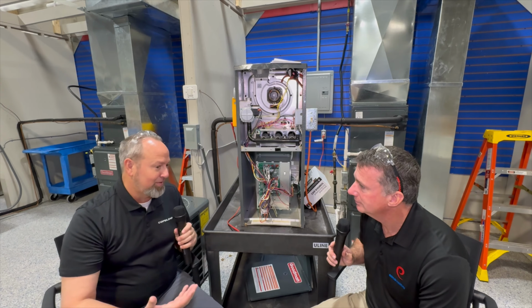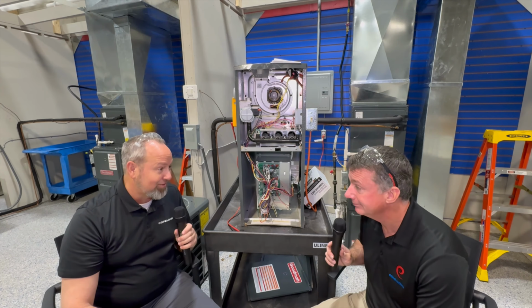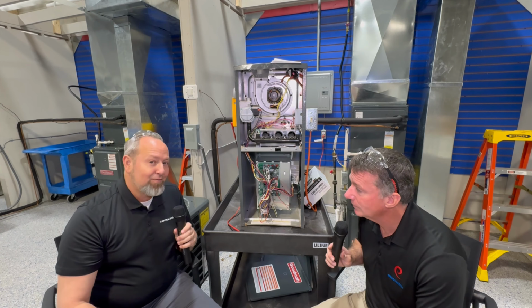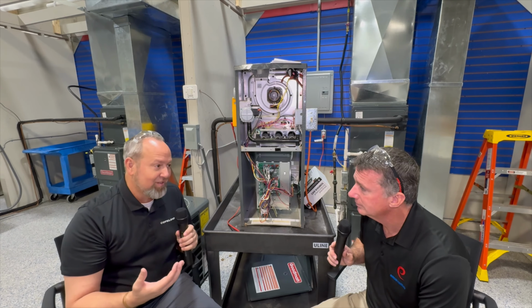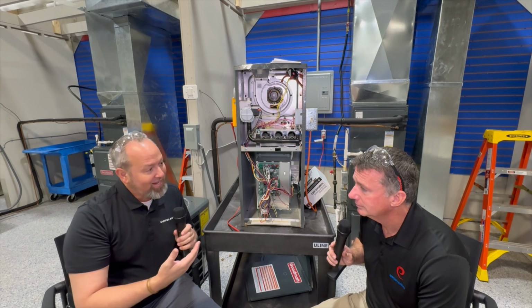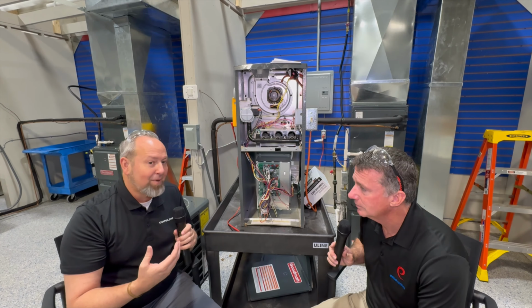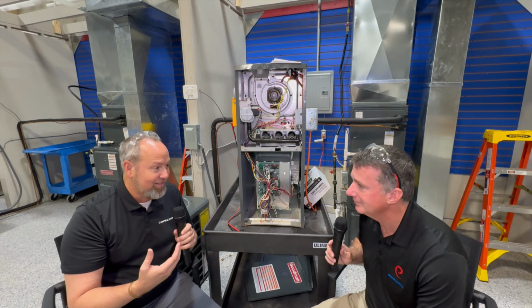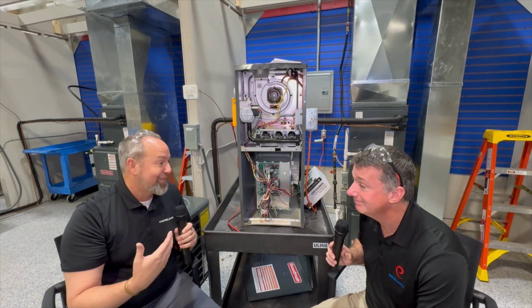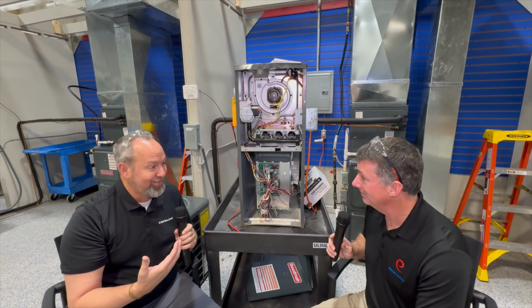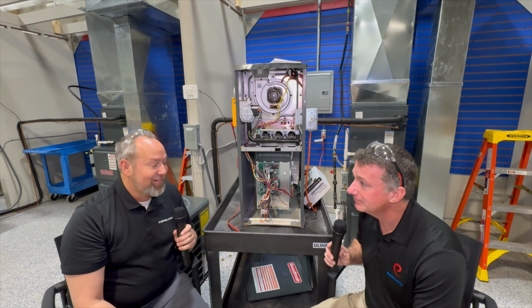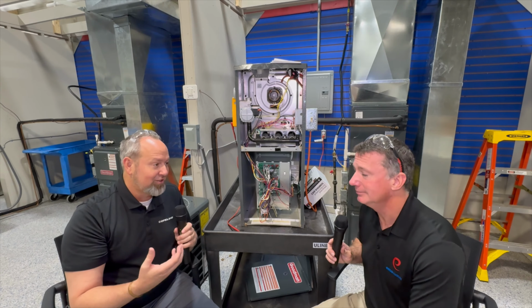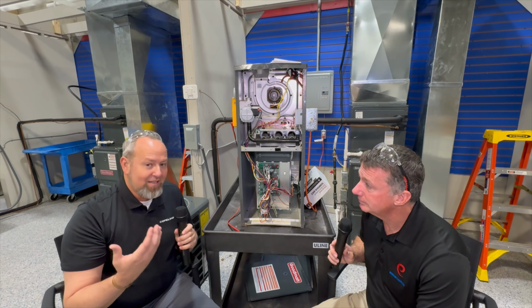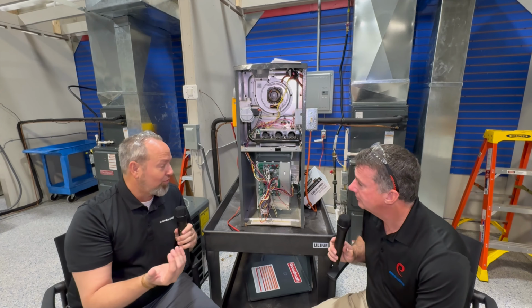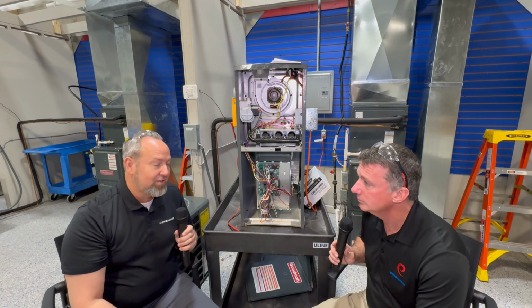And it was before we had induced draft furnaces as well. And if you want to go back a step further than that, even the fan itself had a bimetal mechanical thermostat that stuck in the heat exchanger, and that's exactly what was used to turn the fan on once the heat exchanger got so hot. That's all been digitally changed nowadays. It's all done through timings through a circuit board.